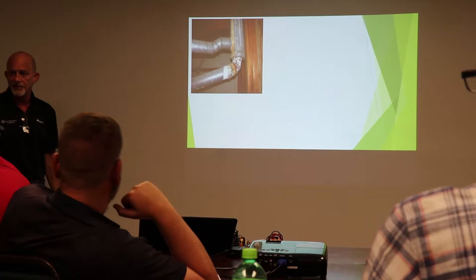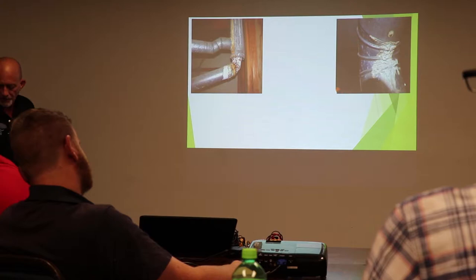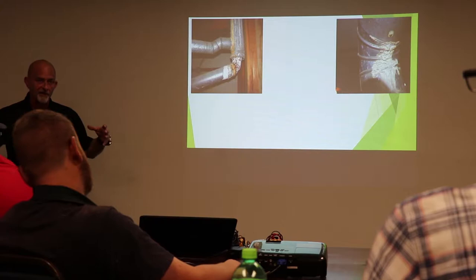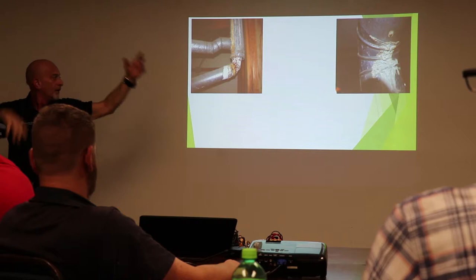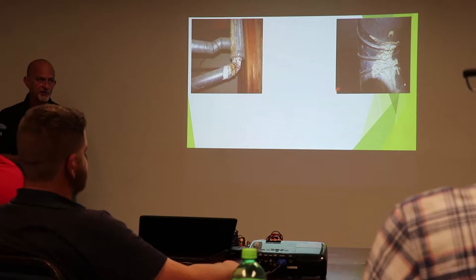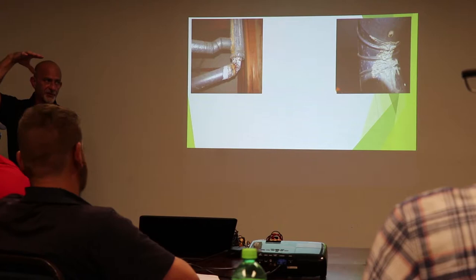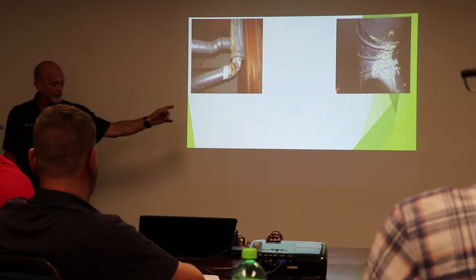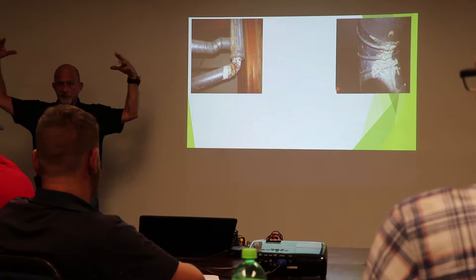You'll see that a lot where an 80% furnace was put in from an old gravity vent. Gravity vent, guys, we took room air, right? Up that chimney to keep it warm. Modern 80% furnace doesn't do that. We're sealed. Our inducer motor on that furnace is only bringing products of combustion in and out of the furnace. Once we get out of that box, natural draft still takes over, but our flue gases are much colder. We can't heat that chimney, so it actually rains inside that chimney.